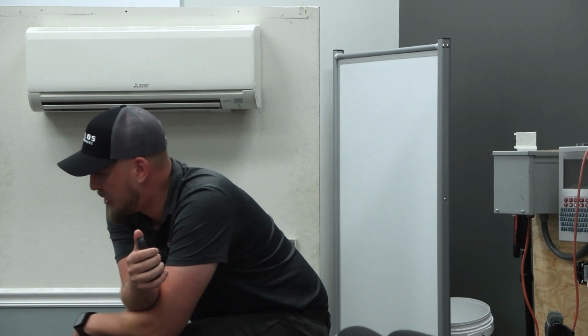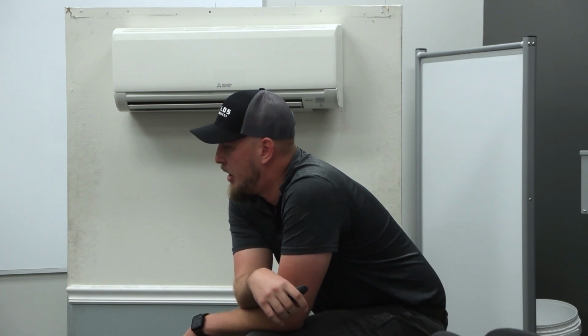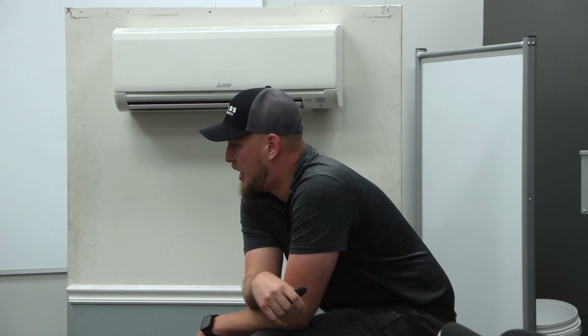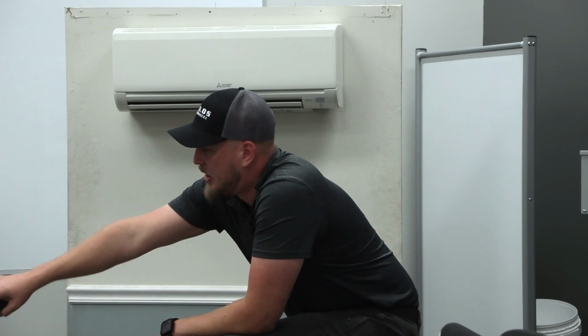I've used it and changed it to cutting off power completely, but that's something you really got to pay attention to. Yep, so per the install manual of, let's say, the orange condensate pump here, between the indoor and the outdoor unit you have a 3-wire high voltage wire. You have 2 legs of 120, and you have a communication wire that the units communicate with. So per the manual, you want to actually break that communication wire with one of the gray or purple wires here.